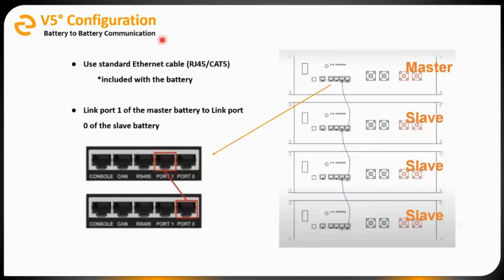First thing you want to check on the batteries is battery to battery communication. In a group of batteries you'll have a master or leader battery, and then slave or follower batteries. We start at the master battery and use those short communication cables to connect one battery to the next, to the next, to the next. These are all just standard Ethernet cables, if you're not using the ones that come with the battery. What's important here is we're going to start at link port 1 on the first battery and go to link port 0 on the second battery, and then link port 1 to link port 0. So at the end of the day, your first battery, port 0 is open, your last battery, port 1 is open. You have to make sure you follow that specific sequence between the batteries.